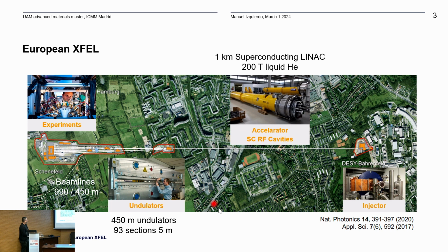So some figures about European X-FEL. It's 3.2 kilometers long from the injector, which is at DESY, to the experimental hall, which is here. There is 1.2 kilometers of superconducting Linac, where all these accelerator cavities are inserted, and they are cooled to 2 Kelvin using 200 tons of liquid helium. Then the long undulators are located in this area. So basically there are 400 meters of undulator sections divided in three SASEs, and each undulator section has 5 meters.